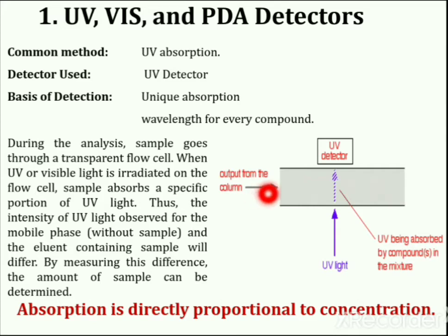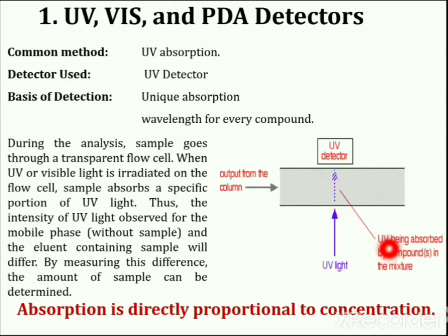The most common detection method includes the ultraviolet absorption method. During the analysis, the sample goes through a transparent flow cell. When ultraviolet or visible light is irradiated on the flow cell, the sample absorbs a specific portion of that light. Thus, the intensity of UV or visible light observed for the mobile phase without sample and the eluent containing the sample will differ. By measuring this difference, the amount of sample can be determined.